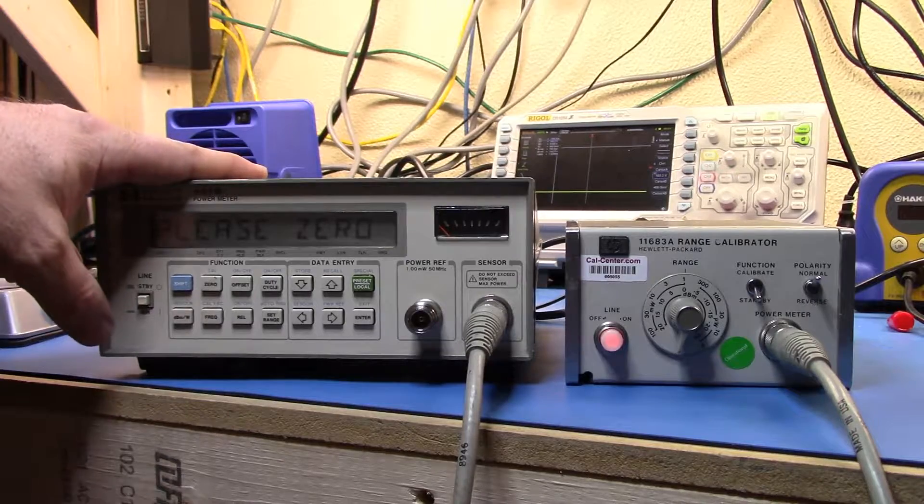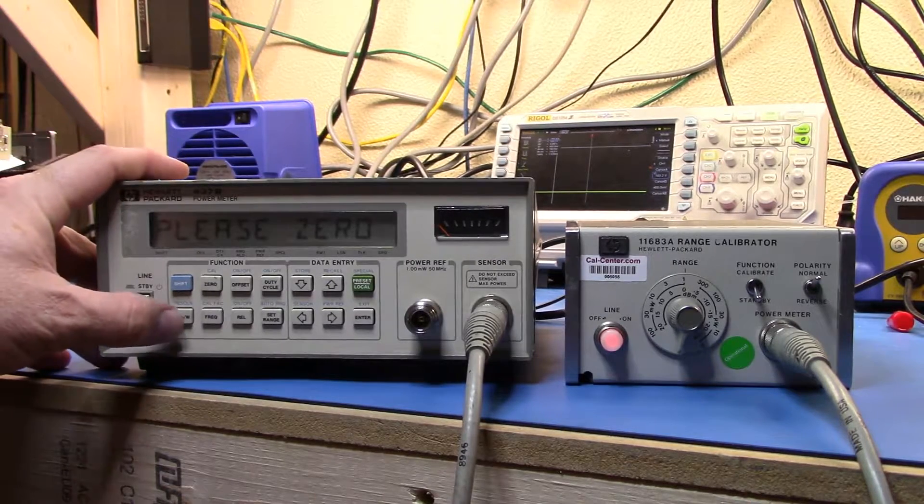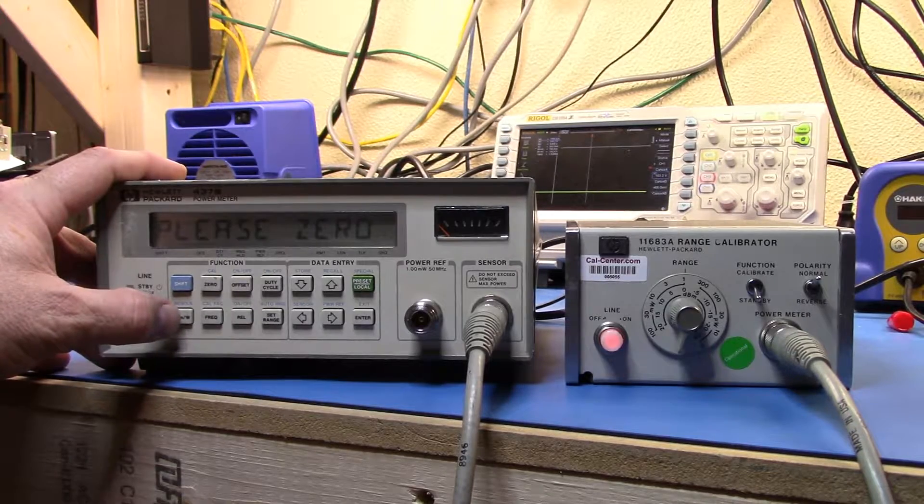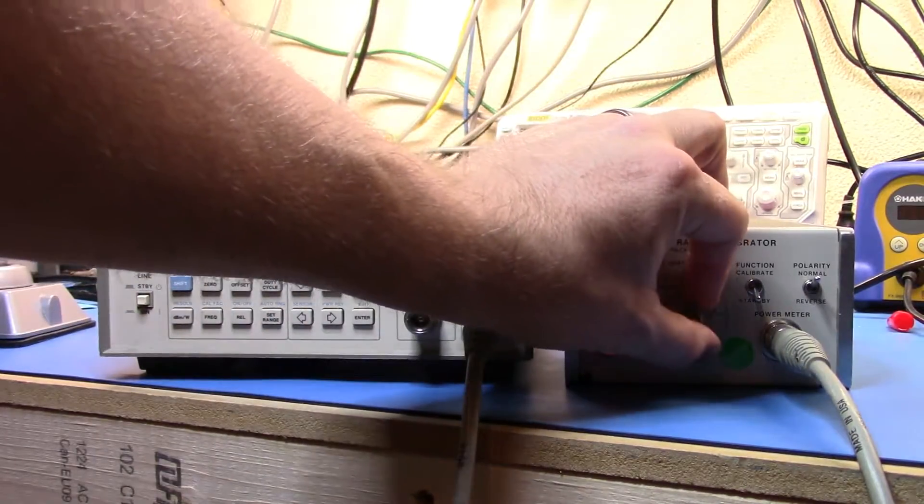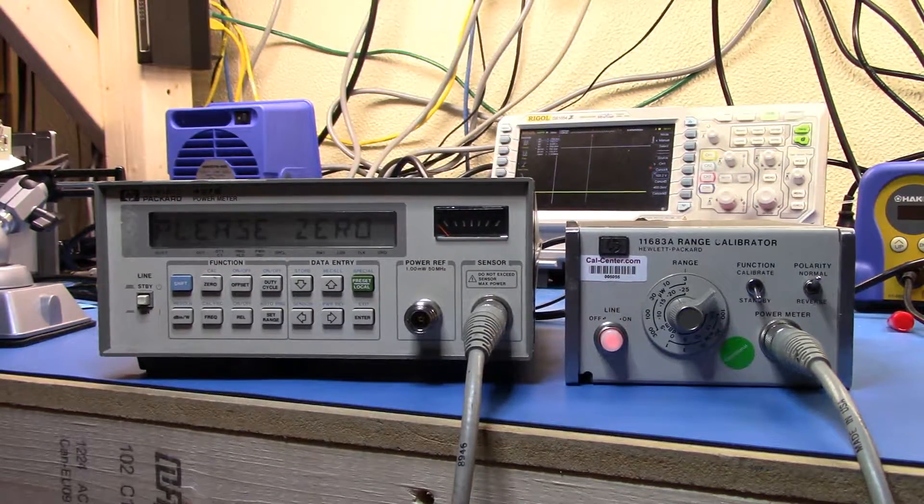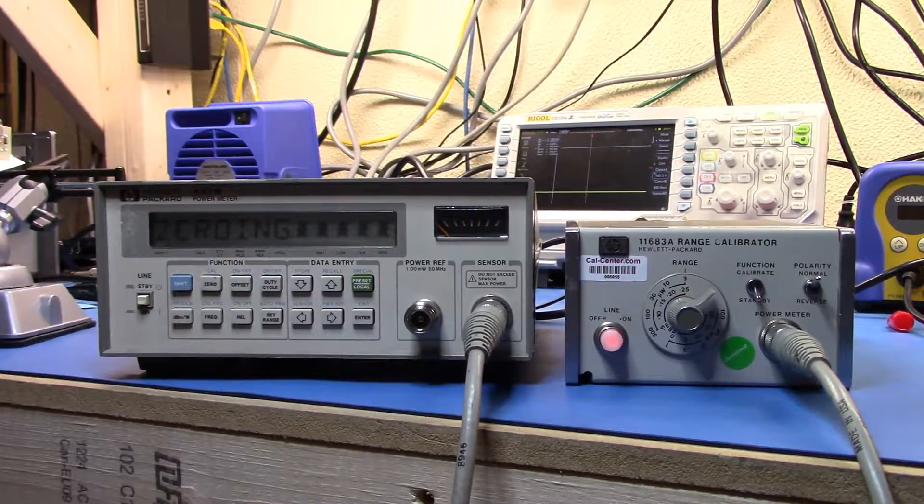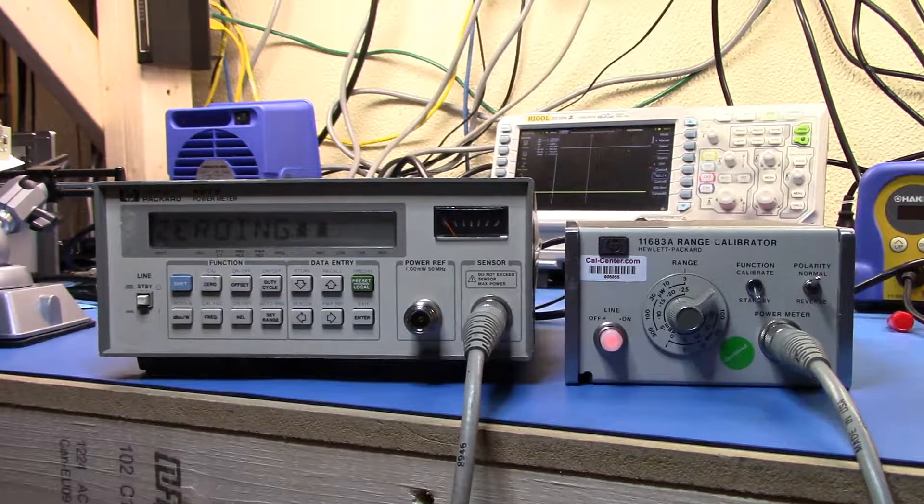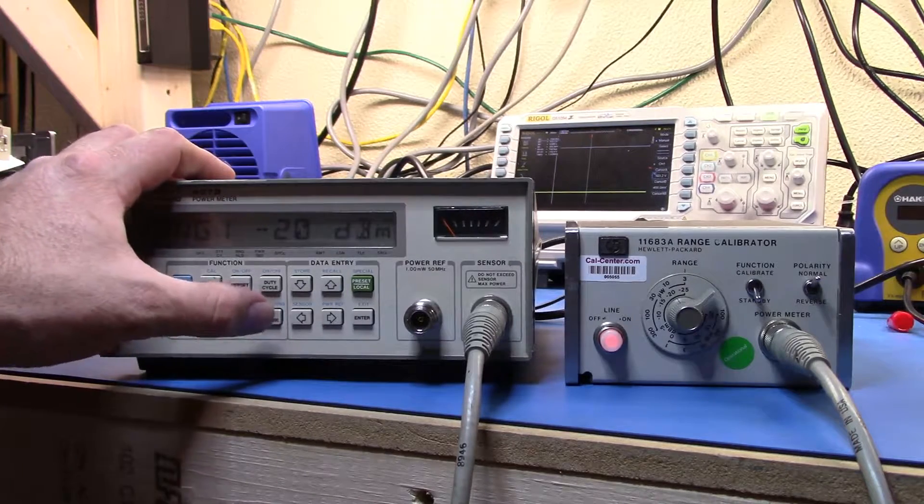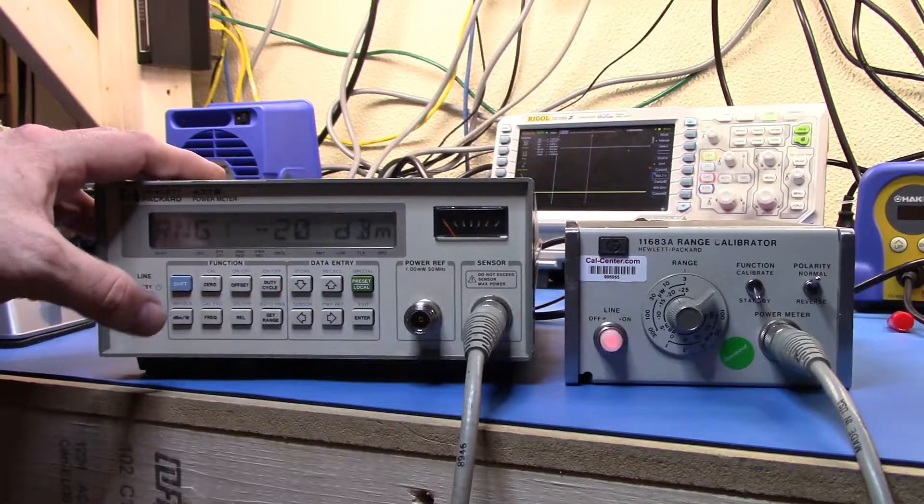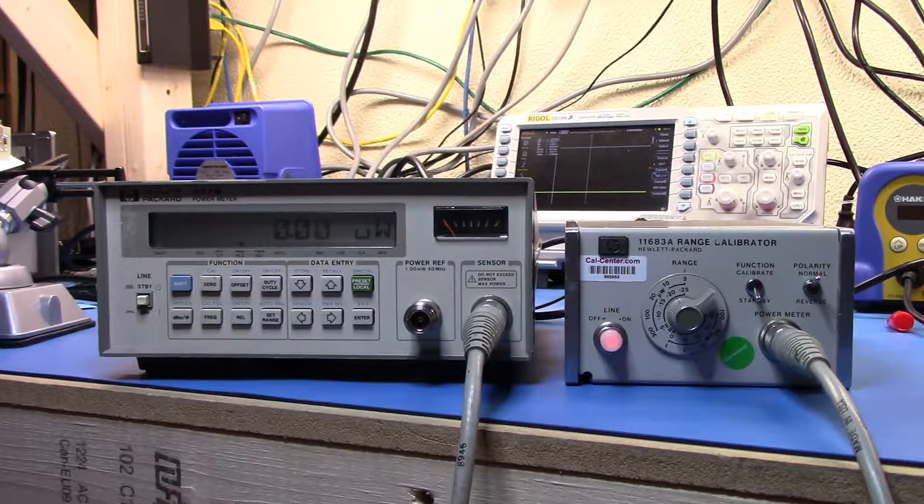So we turn the meter on, we set preset local so we preset the unit and we set it for dB milliwatts. The range calibrator we set to 3 to the 3 microwatt range, we make sure it's on standby, it's turned on and then we press the power meter zero key.